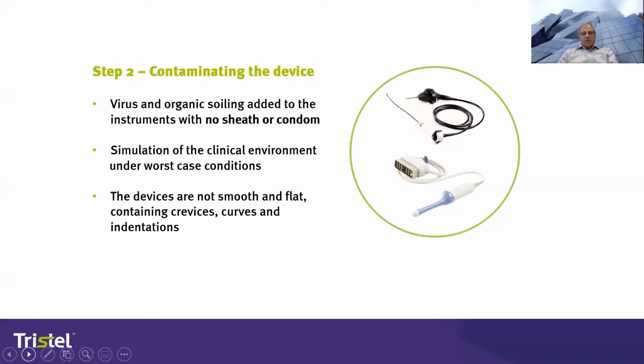Normally, a sheath or a condom is used during clinical procedures, which protects the device and the patient. However, during examination, the occurrence of microabrasions, perforations, or breakages are widely documented in the scientific literature. By negating the use of a sheath or condom, this test provides a worst case scenario in case the cover breakage or inadequate cleaning occurs.